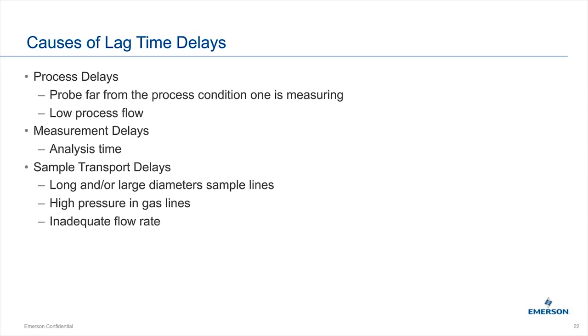There's also the measurement time delay — how long it takes the GC to complete an analysis. For C6+ applications, that's 2 to 4 minutes; for some chemical applications it's 10 to 30 minutes. Then there's the sample transportation delay: how far the probe is from the GC, whether you're flowing gas or liquid, your flow rate, and pressure — high pressure in gas lines means more volume, which takes longer to transport. You want to keep pressure low for gas lines.